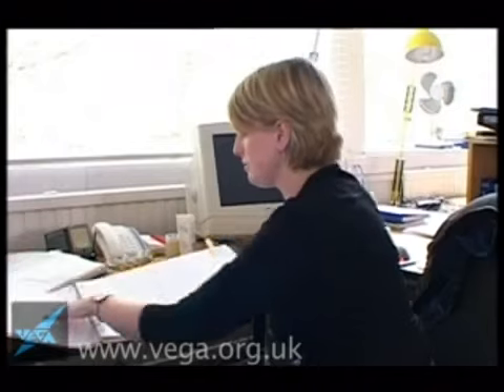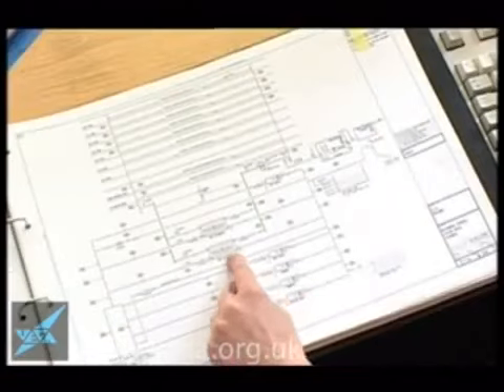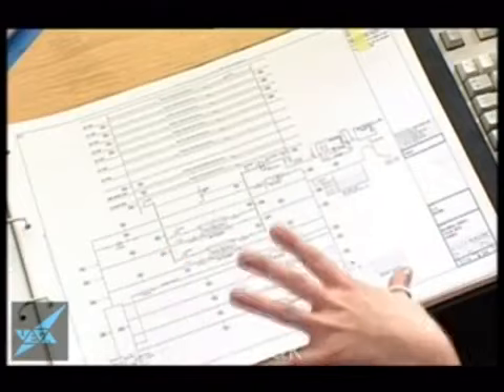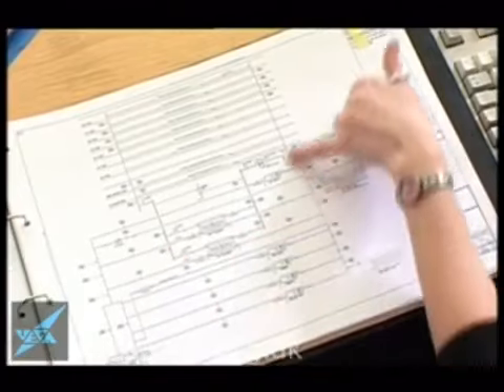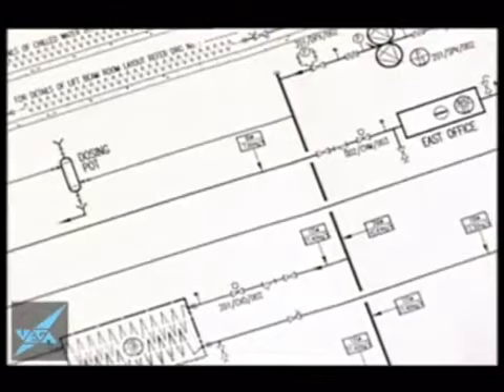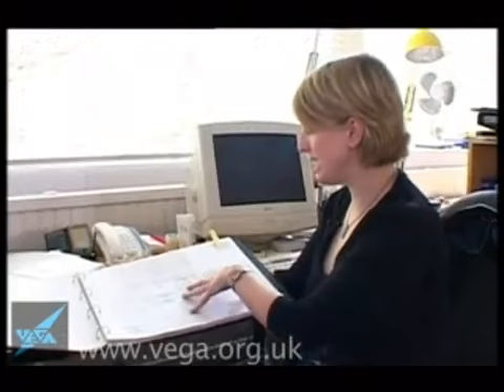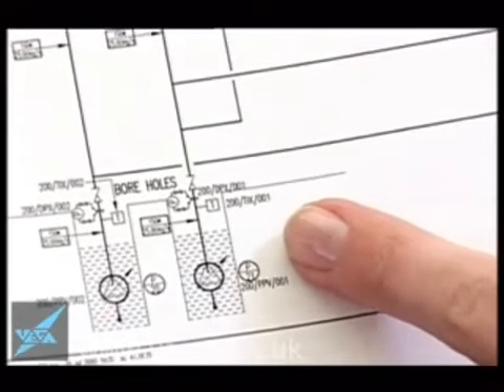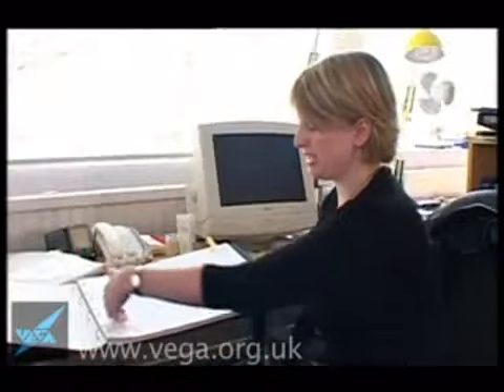Once we've sized the systems, we'll produce a schematic of it, which allows us to size all the pipework runs, all the distribution, all the ductwork, and that all goes onto a schematic, which in our terms is actually the most useful drawing because it shows everything. This is the drawing that the contractor takes and prices against, because it shows every single valve, every connection, everything in the job. This particular schematic is the chilled water schematic, which shows our boreholes, and the cool water comes up from the boreholes and is then distributed through all the systems in the building.